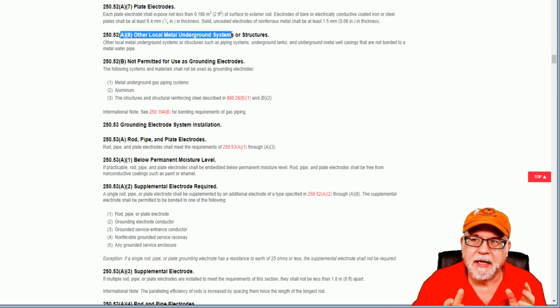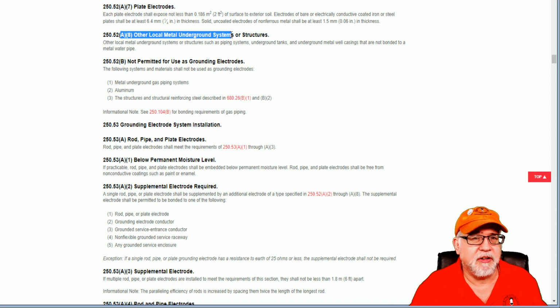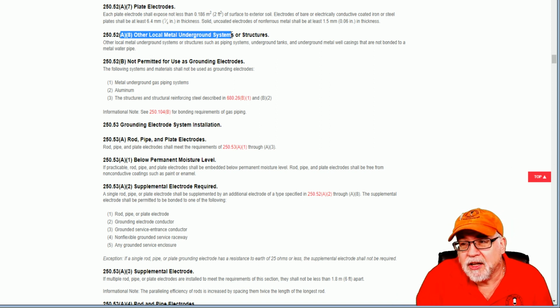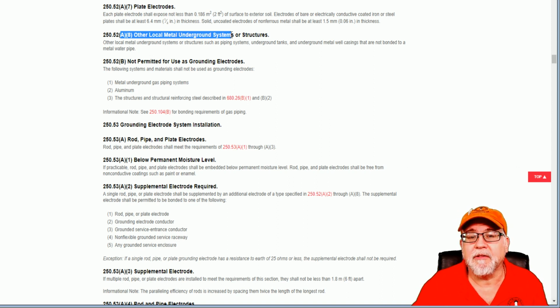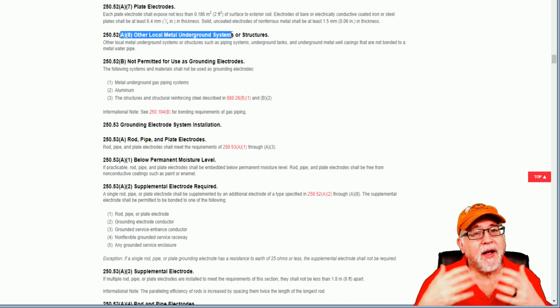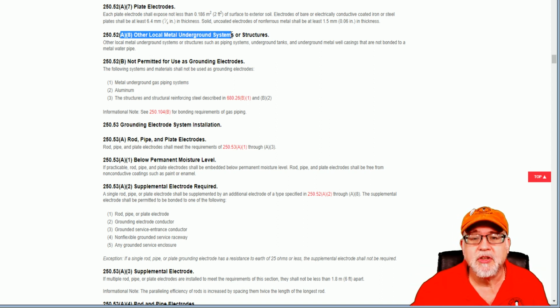Now, typically, I might see engineering drawings that have a concrete encased electrode, but they'll also supplement with ground rods. It's not necessary, but if the engineer calls for that, then you kind of do what they ask you to do, but again, not necessarily required from a minimum standpoint in the code, but they're just going above the minimum requirements, and that's okay too. They might have their reasons. They're the design people. Go with it, okay?